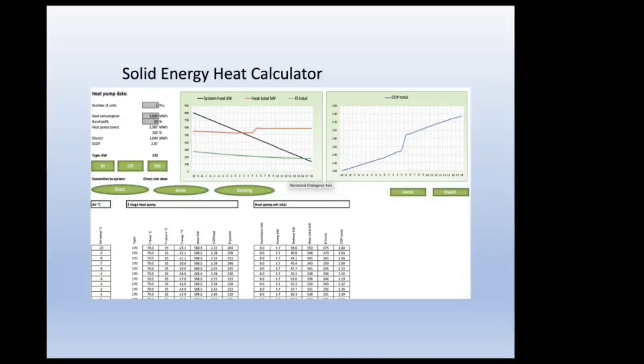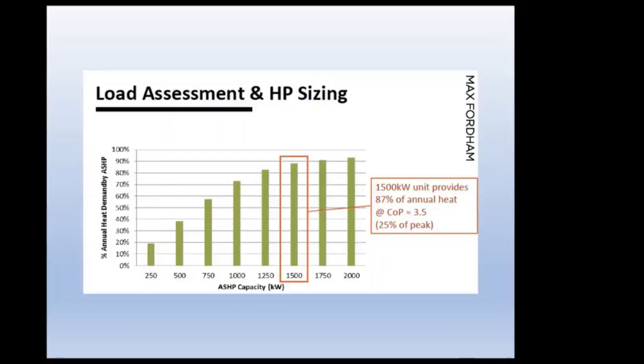This is just another graph to show you that if we design a heat pump to deliver 1,500 kilowatt, that's surrounded by the red line, we can actually deliver just under 90% of the load. And if we do that, rather than supply a 2 megawatt unit, we are reducing the capital cost significantly, and we're allowing the gas boiler to do what it's there for, to top it up, and of course also to provide some resilience.